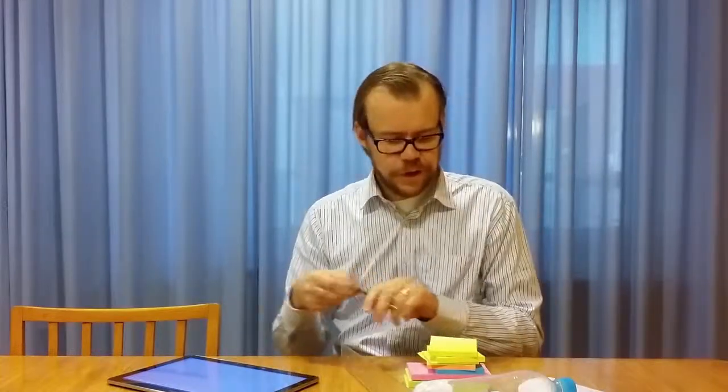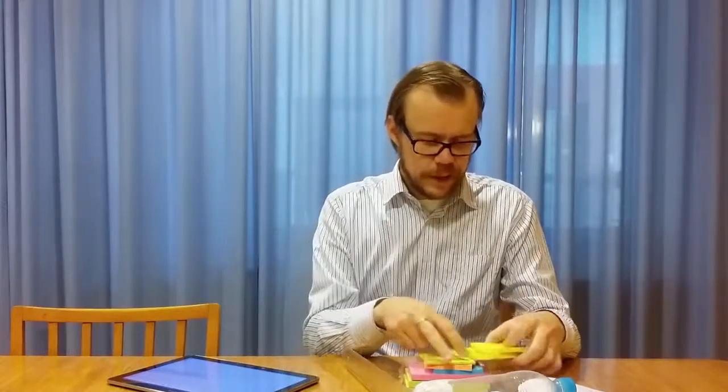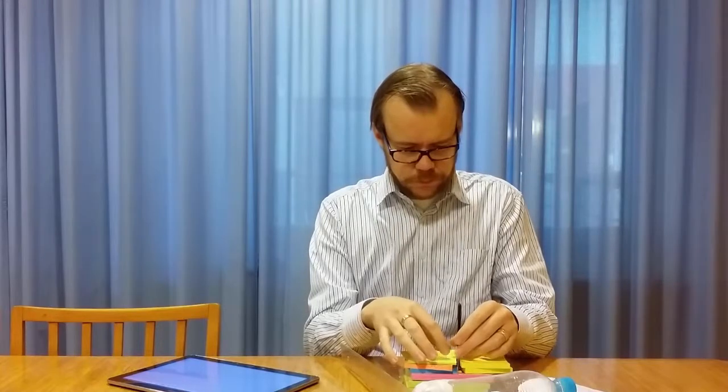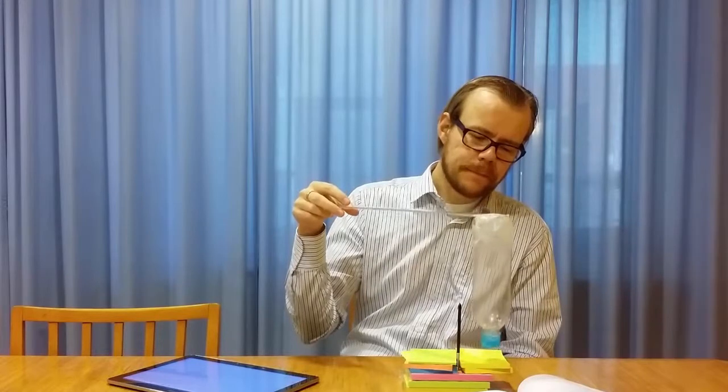Another problem that you can have is that, let's say you have a very sharp object in the substrate, like this, a very sharp thing on the substrate. And then I have my very big tip. And then I come here and start scanning. Then you see when the tip comes close here, it goes over here. And what actually is happening here is that it follows the contour of the tip.